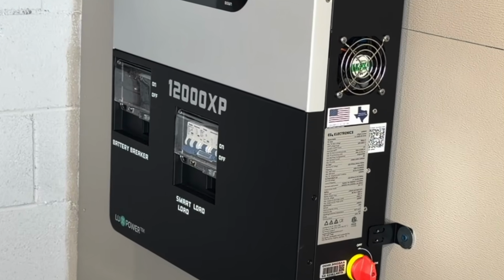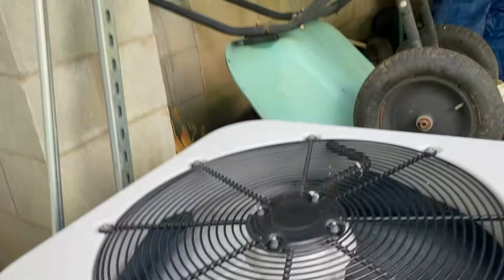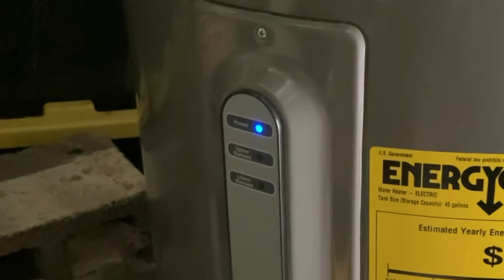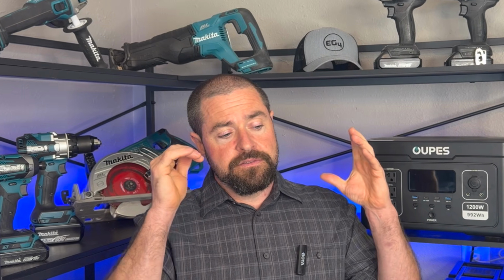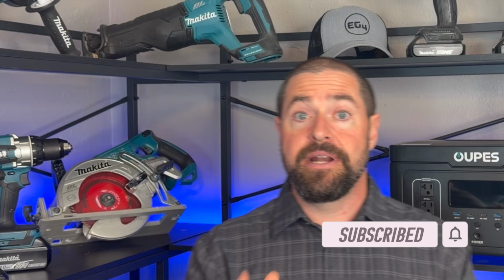Then there's the smart port, which is programmable. You can set it so that once your battery bank reaches 50% depth of discharge, it turns that large load off and saves the rest of the bank for more critical loads. You could put something like your air conditioning, an EV charger, a heating system, or a water heater on there, and kind of set it and forget it. That way, during an outage, all your loads are backed up, but once the battery gets drained down, it'll shed that load and save battery power for the critical loads, so you can get through an extended utility outage without draining your battery bank.